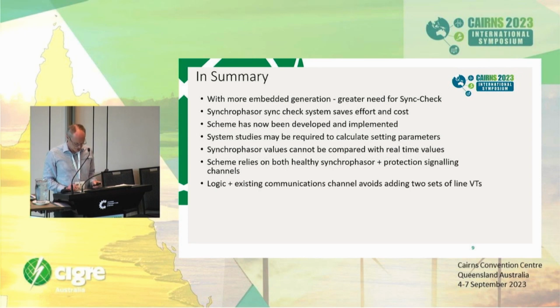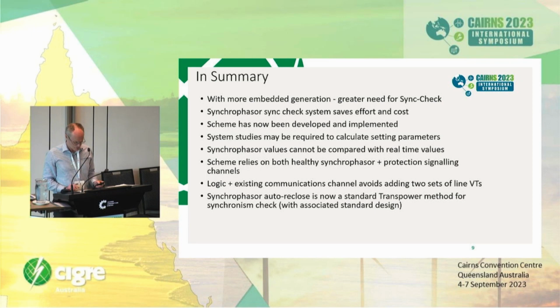This implementation avoids adding two sets of line VTs. Synchrophasor auto-reclose is now a standard Transpower method for synchronism check and has an associated standard design. There has been early positive experience with successful auto-recloses. Transpower continue to monitor and apply the scheme.